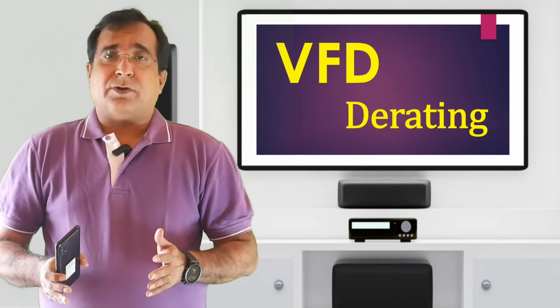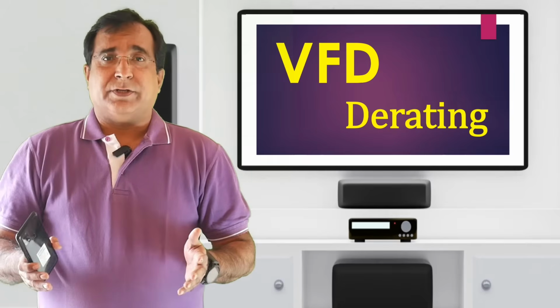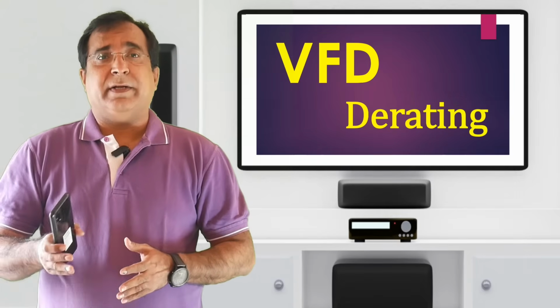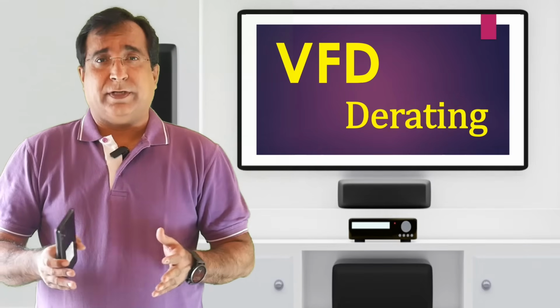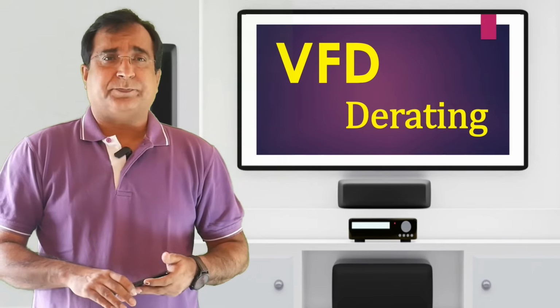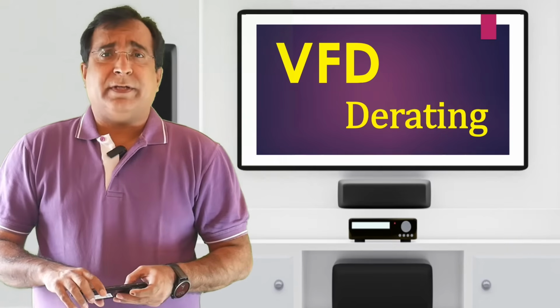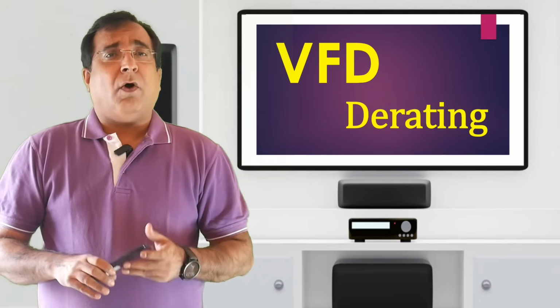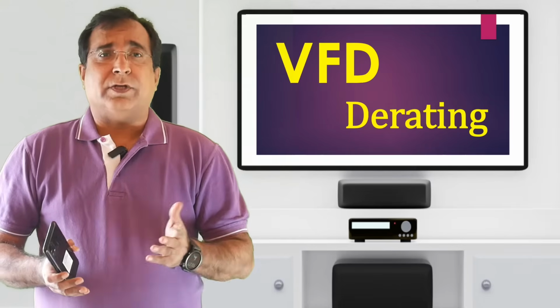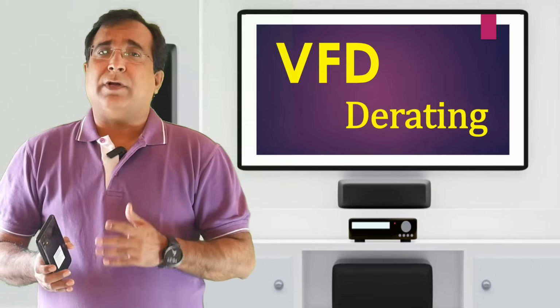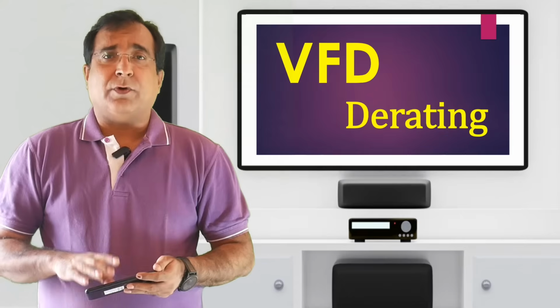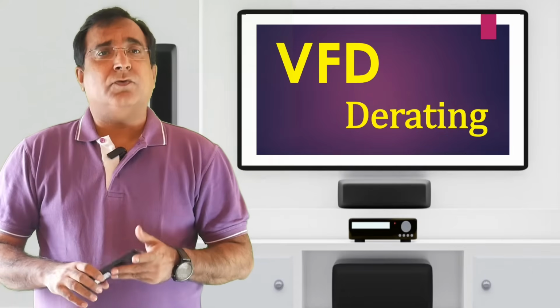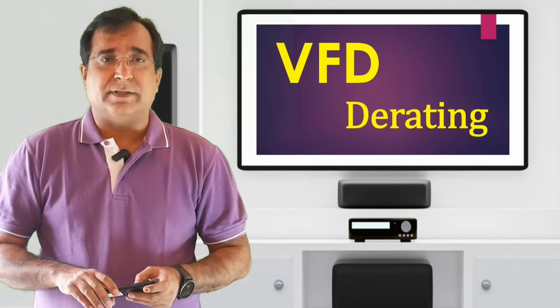But if the VFD is installed at some remote location where air conditioning is not possible, then the ambient temperature rises up to 45 to 46 degrees in the summer season. Then derating of the VFD is the only solution. Or you will be getting calls from the control room for frequent tripping, or it may fail permanently on the hardware part. So calculate its derating according to the rise in temperature in the peak summer season.